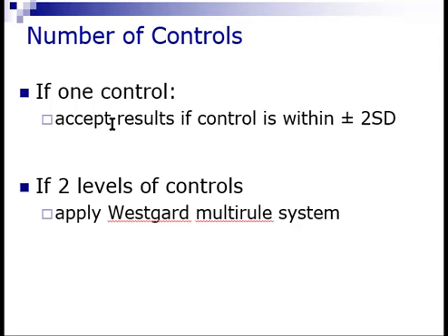No? So the values are said to be in control if they fall within the plus minus 2 SD. Tapos, kapag kahit isang value lang, no, na lumampas ng plus minus 2 SD, considered na yun siya agad na out of control. Then we reject the run and do corrective action. Okay? So yun lang po yung kailangan tandaan. Kapag, again, yung isang laboratory, meron siyang machine and that machine nag-utilize lang ng isang control.